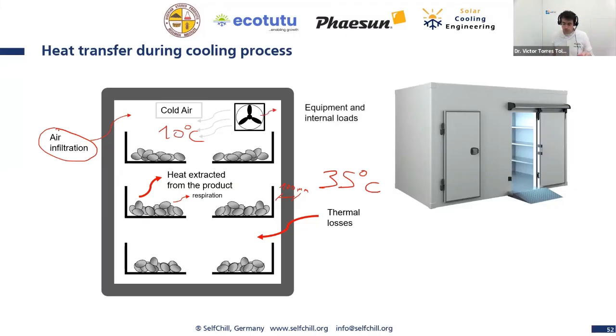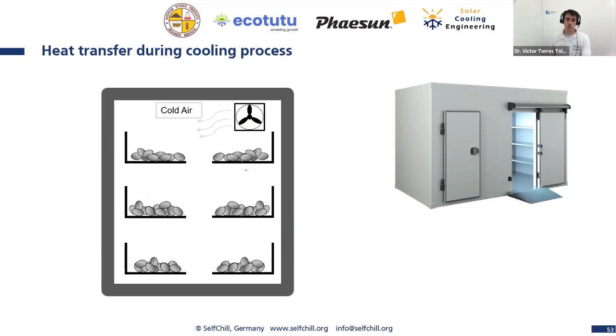And what else? What about if we have equipment inside the cold room? If we have, for example, the fan consuming, I told you before, 40 watts for both water pump and fan. I can tell you already our fan has consumed 27 watts. So this electricity consumed inside the cold room will also have a cooling demand. The same if persons are going inside the cold room. Every person emits a certain amount of heat energy to the environment, and this also needs to be considered for the design of a cold room.